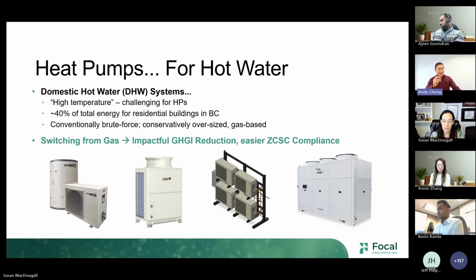I think we need to stop thinking about these as instantaneous systems, because really they're a battery. One of the design implications of going to heat pump water heating is it helps these heat pumps work with a large volume of storage. I mention this because it's actually a strategy we can use to reduce impact on peak electrical demand as well. So think of your storage tank as this big battery of hot water that's ready to go. If you have a shower at 6 in the morning and throw your kids in the bath at 6 p.m. at night, there's about 12 hours where you're not anywhere close to peak hot water demand - that's the time you're charging the battery. You can exhaust the whole battery, drain it down, take all the hot water out, it'll fill up with cold again and take some time to charge up. The more volume you have, the more liberty you have to draw off that peak demand, and the slower and more lenient you can be with how quickly the system restores it.